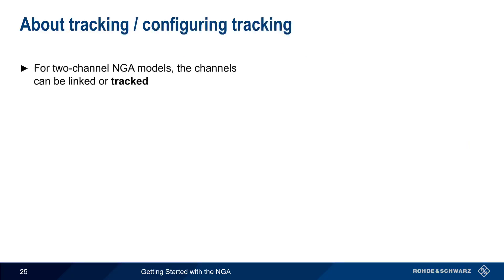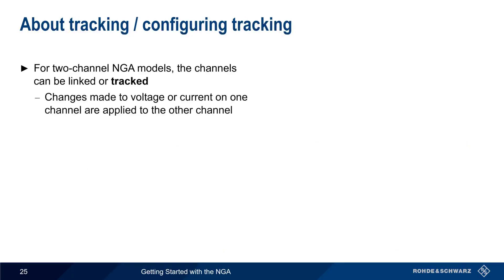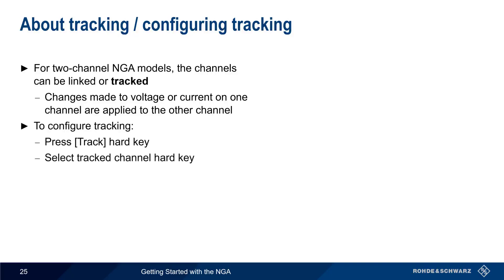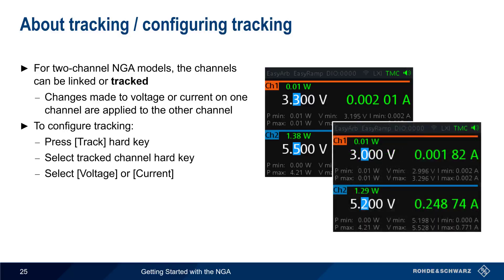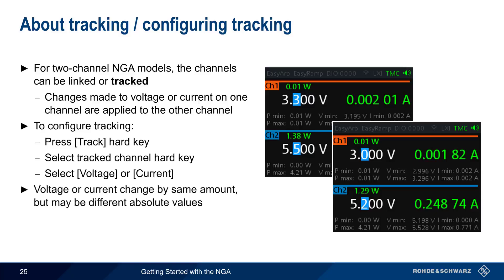On two-channel NGA models, the channels can be linked or tracked. Tracking means that changes made to voltage and current on one channel are applied to the other channel. To configure tracking, press the track hard key, select the hard key for the tracked channel, and then select voltage or current. The blue highlighting in both channels shows the values that are being tracked, and changing the value in one channel automatically changes the other channel by the same amount. Note that although voltage and current will change by the same amount, the absolute values may be different in each channel.